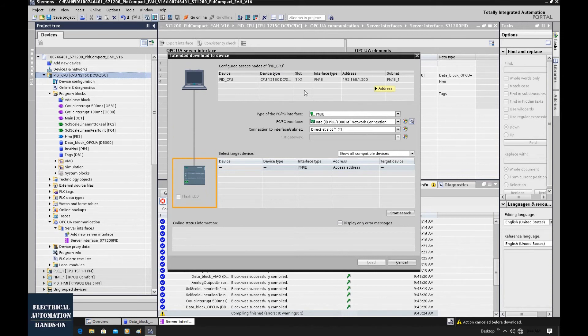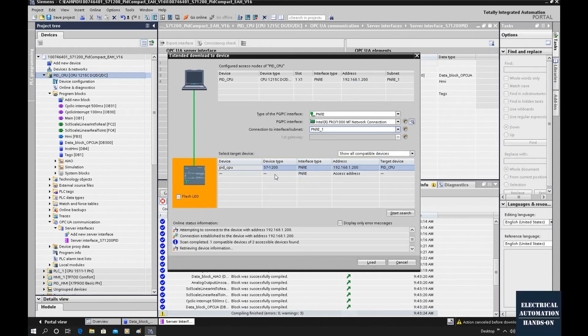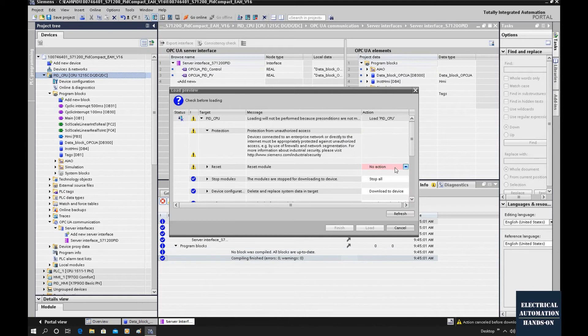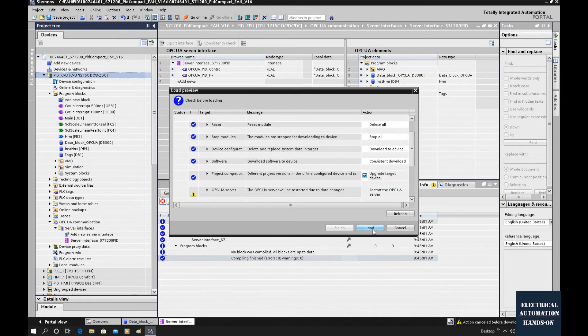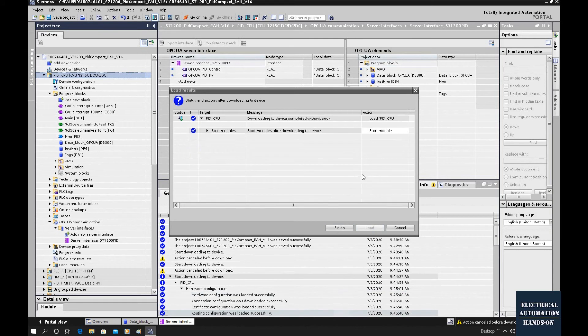With this configuration, the OPC UA server function will be activated inside this controller. Start the search and make sure the IP address of this controller is 192.168.1.200. I will download to this CPU. Since we need to download the hardware configuration, the controller needs to be stopped first. Select 'Start the module' and once we hit Finish, the controller will start.